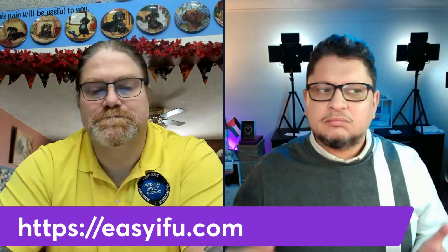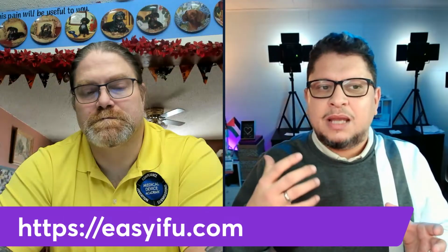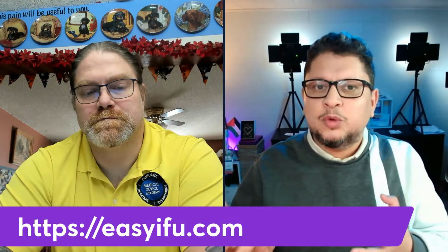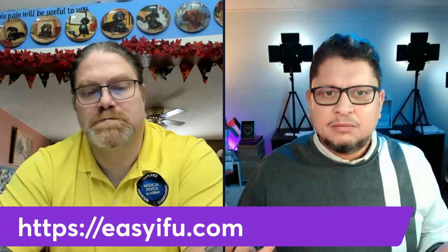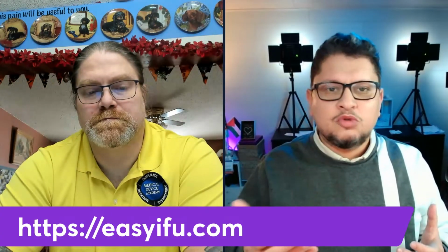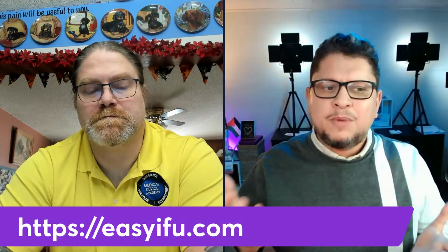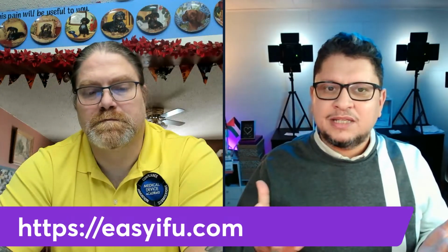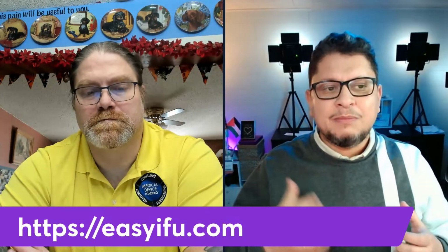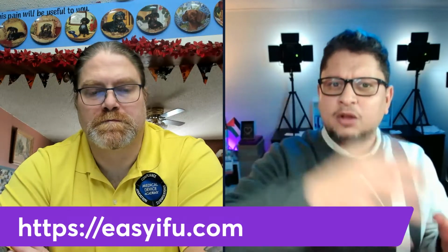And we found out there are some rules in terms of, for example, cybersecurity. You have to have cybersecurity for the website, because if it's an emergency, for example, and you have to get the eIFU quickly, and you are under a bug or your server is down, then you have big trouble for the patient. So there are cybersecurity rules where you have to prove that you have passed some cybersecurity testing. Plus you also have to have some backups. So for easyIFU, we have 3 server backups, which means that if one is down, there is one server that will send to another one, and then to another one.